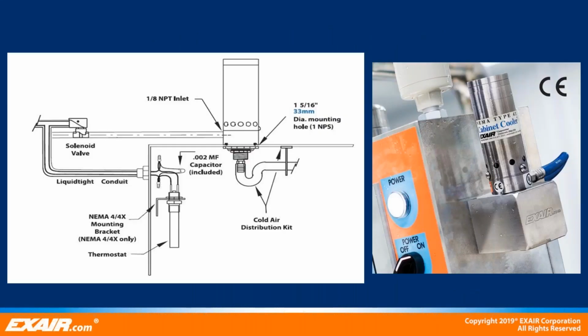Cabinet coolers mount to the enclosure through a drilled hole or a standard electrical knockout. The NEMA Type 12 cabinet coolers may be mounted on the top or the side of the panel, while the NEMA 4 and 4X cabinet coolers must be mounted on the top of the panel or on the side of the panel in a vertical position to maintain their NEMA integrity. If there is a need to mount a NEMA 4 or 4X cabinet cooler on the side of the cabinet, we do offer a side mount kit to make this possible without impacting the NEMA integrity of the cabinet. You can see that in the right photo.